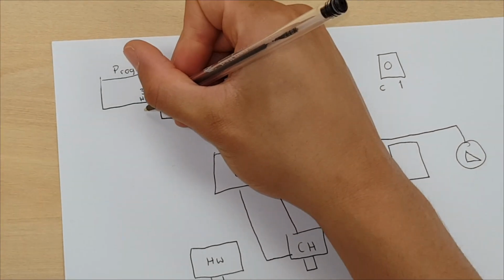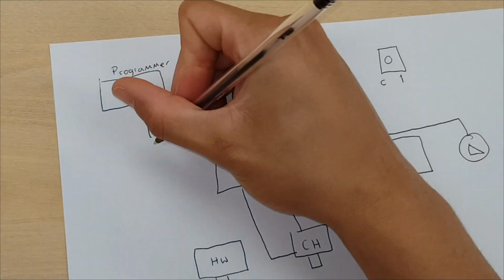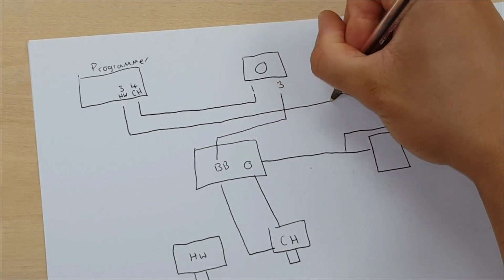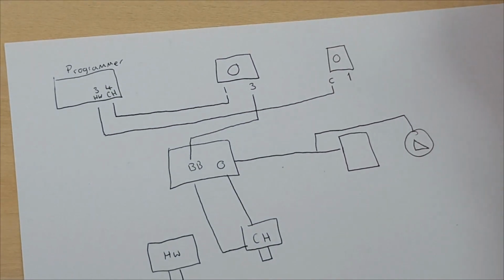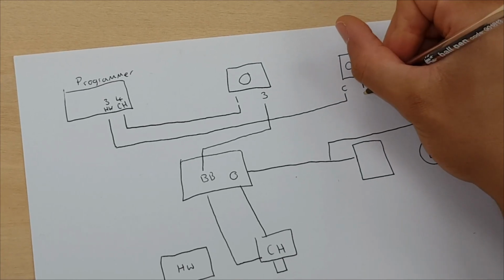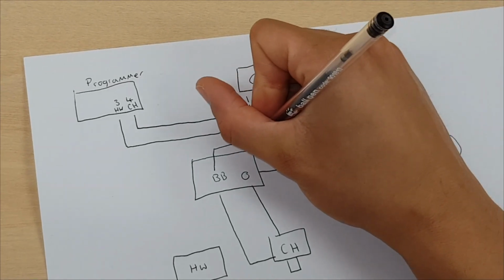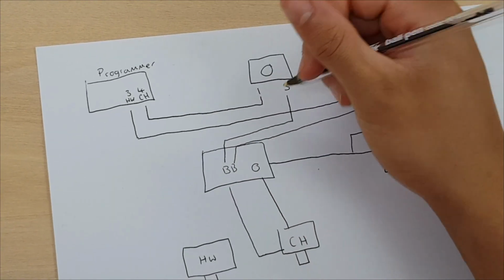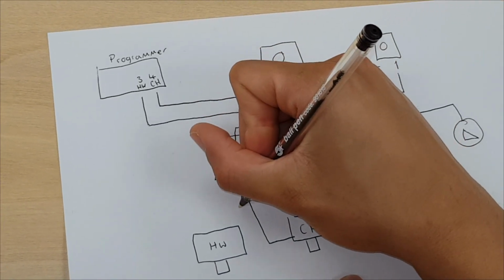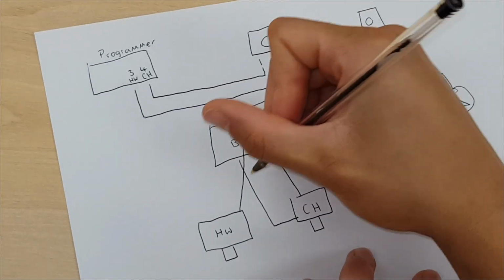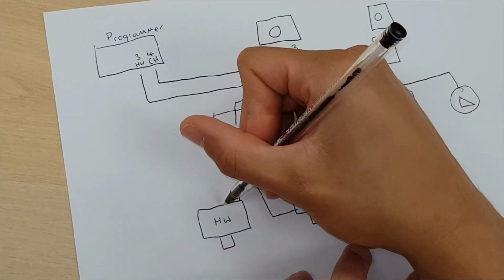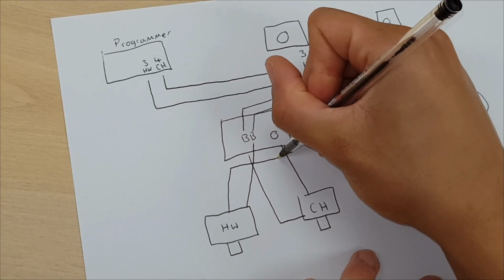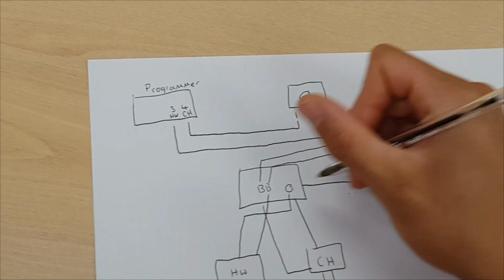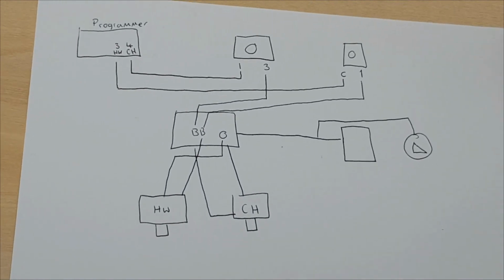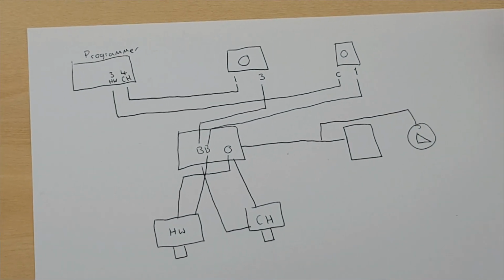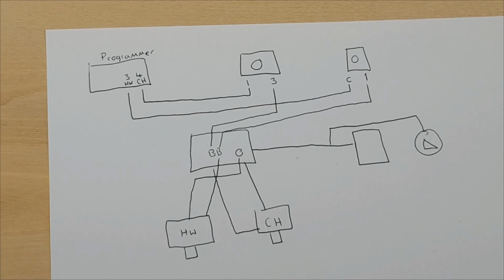Right, now let's look at the hot water. Okay, so go from terminal 3 on our programmer over to our cylinder stat, the common. Then from terminal 1, we go to our live again, the brown, which comes down to the hot water zone valve, which also connects to the orange, which then goes to the pump and boiler once again. Excellent. Well done.